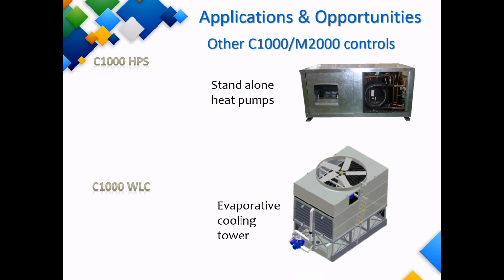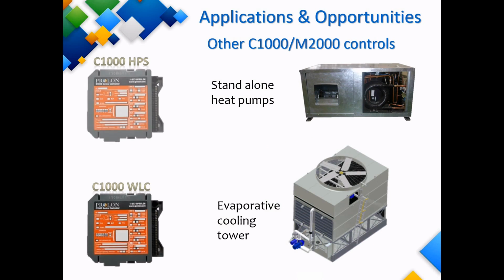Here is a nice little combo application. If you have a building which has a water loop, and this water loop is supplying multiple heat pumps, Prolon can control the water loop and every heat pump as well. We have a dedicated water loop controller which can operate a simple cooling tower with a boiler. Prolon's heat pump controller can control either water-sourced or air-sourced heat pumps with optional supplemental heating strip.